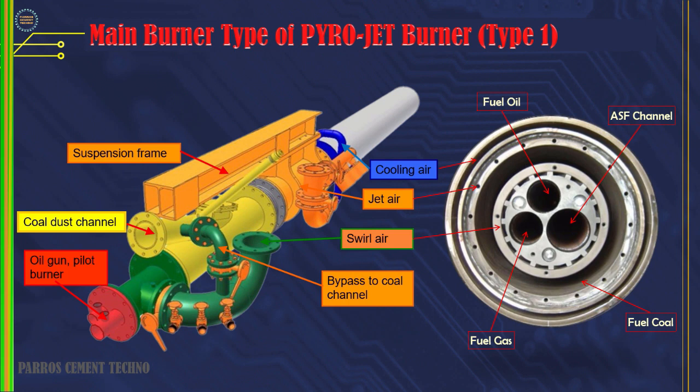This is a PyroJet burner. This type of burner uses a roots blower separately for axial and radial air, so they do not affect each other. This is different from burners that use only one fan for axial and radial air. Primary air pressure reaches 800 mbar for axial air, and 150 to 250 mbar for radial or swirl air.